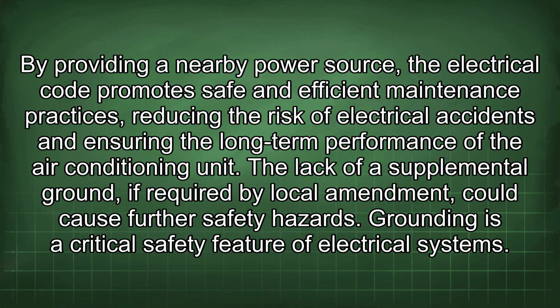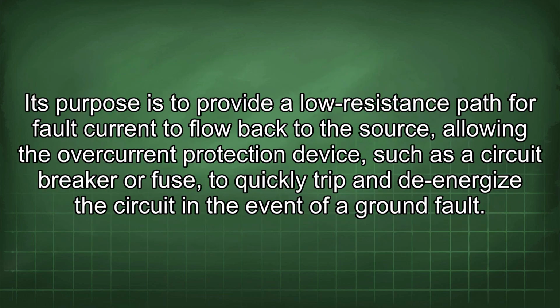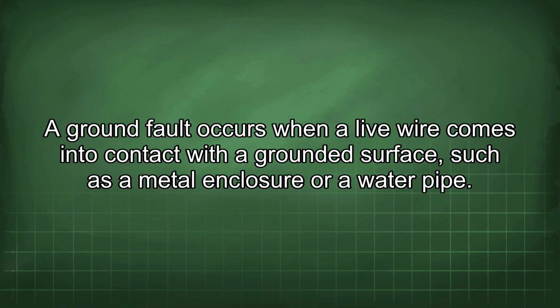The lack of a supplemental ground, if required by local amendment, could cause further safety hazards. Grounding is a critical safety feature of electrical systems. Its purpose is to provide a low-resistance path for fault current to flow back to the source, allowing the overcurrent protection device, such as a circuit breaker or fuse, to quickly trip and de-energize the circuit in the event of a ground fault. A ground fault occurs when a live wire comes into contact with a grounded surface, such as a metal enclosure or a water pipe.